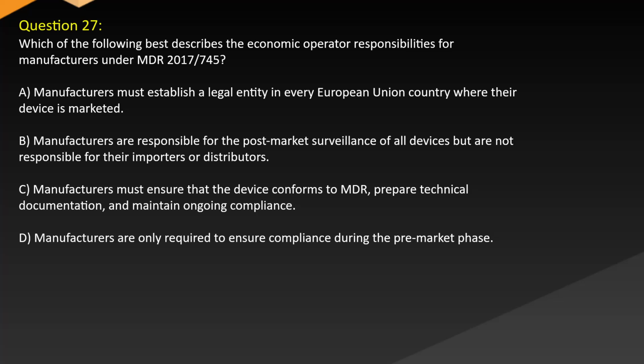Question 27. Which of the following best describes the economic operator responsibilities for manufacturers under MDR 2017-745? A. Manufacturers must establish a legal entity in every European Union country where the device is marketed. B. Manufacturers are responsible for the post-market surveillance of all devices, but are not responsible for their importers or distributors. C. Manufacturers must ensure that the device conforms to MDR, prepare technical documentation, and maintain ongoing compliance. D. Manufacturers are only required to ensure compliance during the pre-market phase.